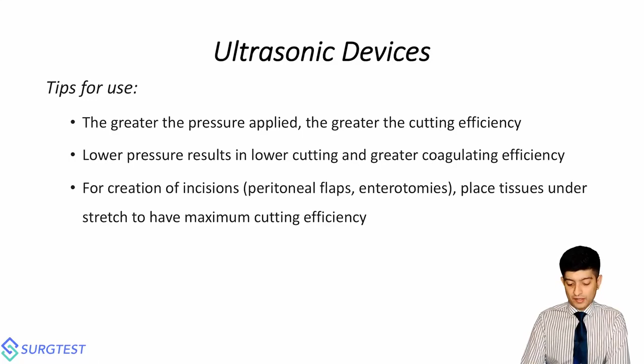So if you're holding a vessel, you want to keep the jaws just apart, not entirely press the tissues down, because your cutting effect is going to be increased, and you want to use the minimum setting on the ultrasonic device to be able to get good hemostasis. If you want to create an incision, say peritoneal flaps or enterotomies, place the tissues under significant stretch to have maximum cutting efficiency. I have an analogy for this.